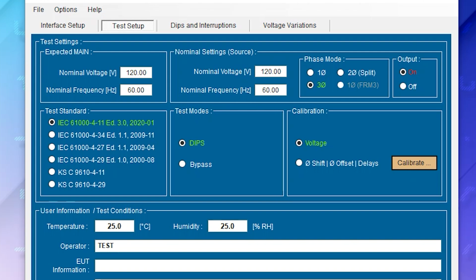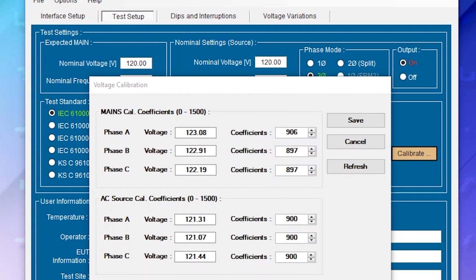The voltage measurement calibration is designed to measure the incoming mains voltage on all three phases to be sure it's within the ranges for IEC 61000-4-11 and IEC 61000-4-34. Just below that, we have the phase shift, which calibrates the AC source phase with phase A of the AC mains input. Let's start with the voltage. To do that, be sure that voltage is selected in the calibration section and then hit calibrate. Here's the voltage calibration menu.